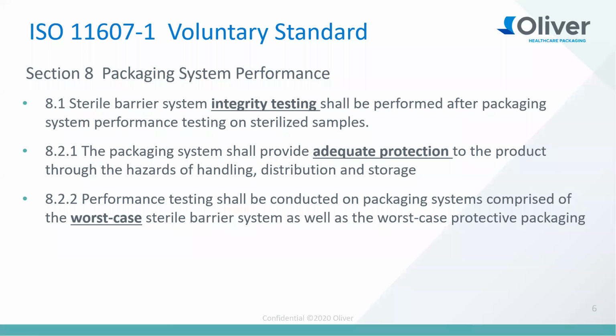So 11607 is a voluntary standard. The standard itself has two parts: part 1 and part 2. Part 1 focuses on the packaging system performance and stability, while part 2 focuses more on the process validation and process verification. So for today's webinar, we'll focus on part 1 and specifically on section 8. The performance focuses on distribution testing, transportation simulation, while stability involves accelerated aging. So this basically means that you're subjecting your samples to distribution simulation, and then you test the sterile integrity, such as bubble leak or dye penetration, following the schedule.